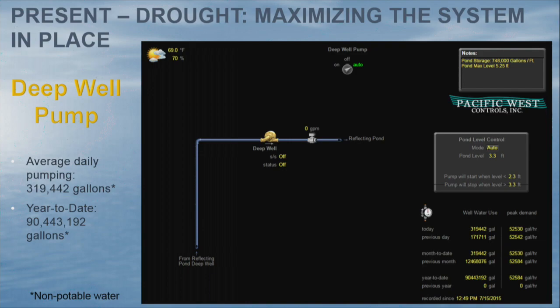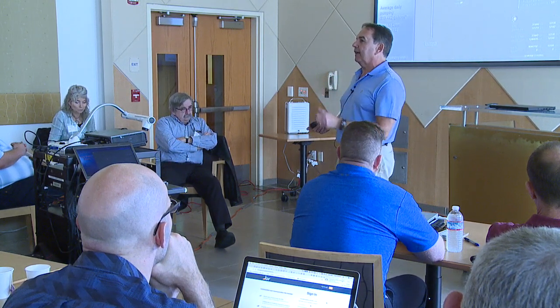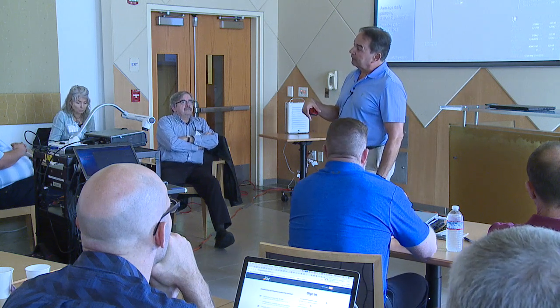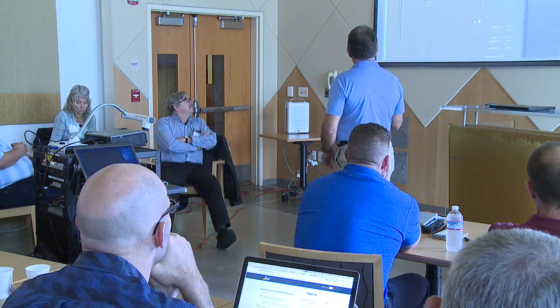Literally millions of gallons of water move through the system. But one of the really cool things is that on days like this, this program has the ability to look into the forecast, 8 to 10 days ahead. If it sees rain coming, it will actually adjust the lake levels to make sure there's ample capacity to store the water. Otherwise, it goes off campus. So it actually changes the set points on its own, which is very interesting.